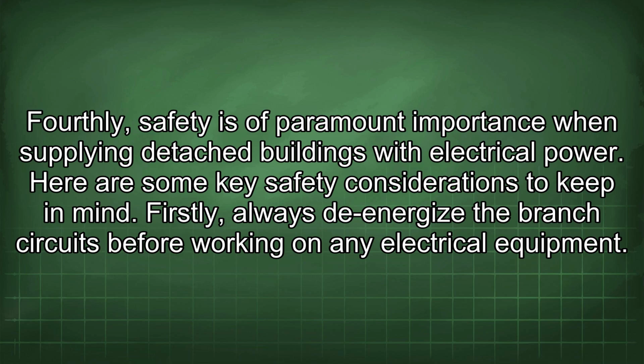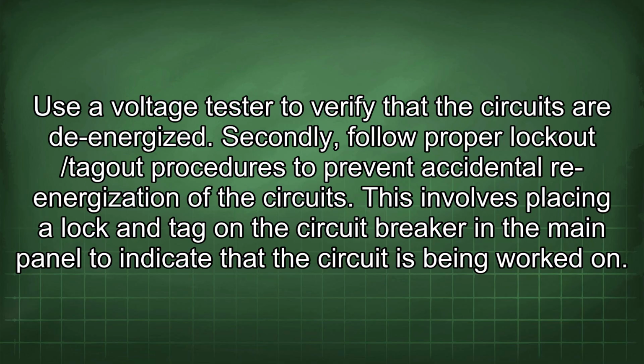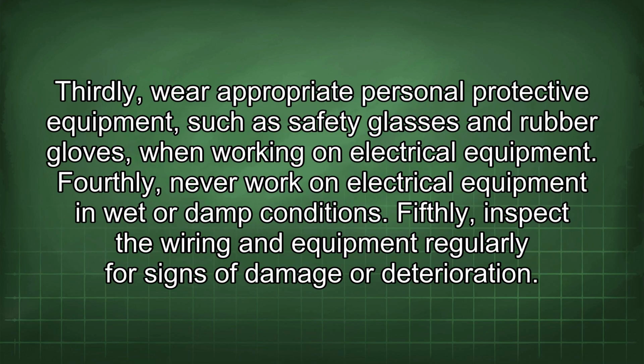Firstly, always de-energize the branch circuits before working on any electrical equipment. Use a voltage tester to verify that the circuits are de-energized. Secondly, follow proper lockout/tagout procedures to prevent accidental re-energization of the circuits. This involves placing a lock and tag on the circuit breaker in the main panel to indicate that the circuit is being worked on. Thirdly, wear appropriate personal protective equipment, such as safety glasses and rubber gloves, when working on electrical equipment. Fourthly, never work on electrical equipment in wet or damp conditions.